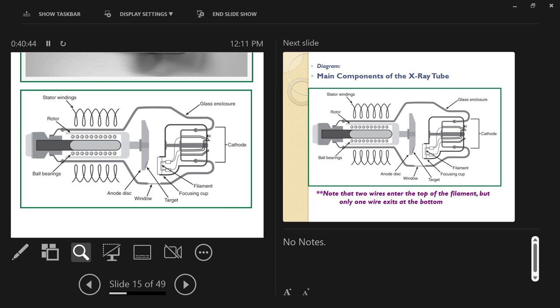If an x-ray tube is heated up or cooled down too quickly it's still at risk, but Pyrex makes it much less likely. X-ray tubes have to heat up and cool down throughout their entire serviceable lifespan of 10 years or more. Pyrex is a brand name; exactly how it differs from regular glass isn't entirely clear, but it's engineered to retain and lose heat without significant molecular structure change.